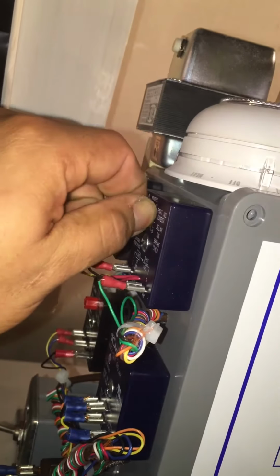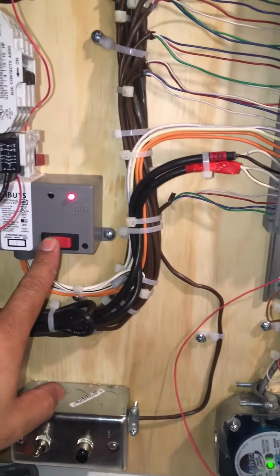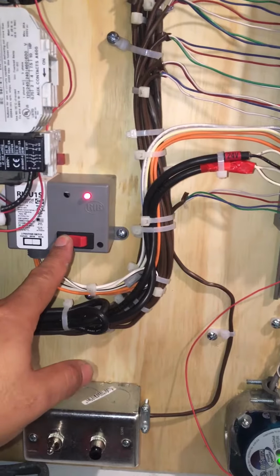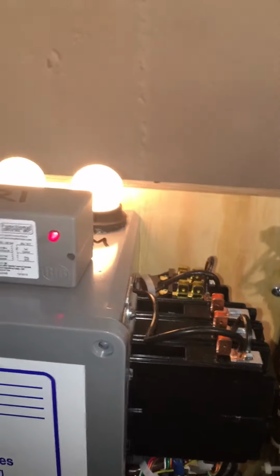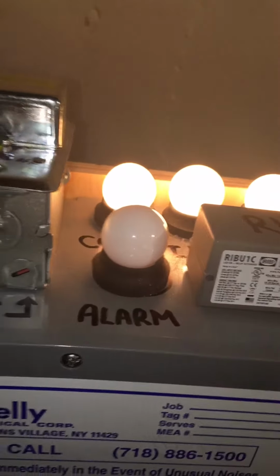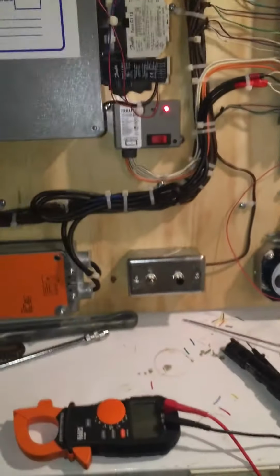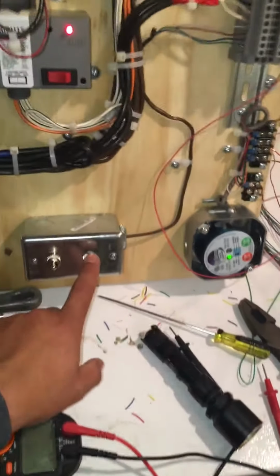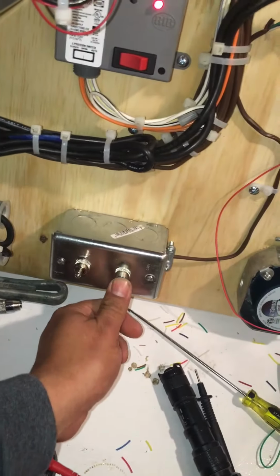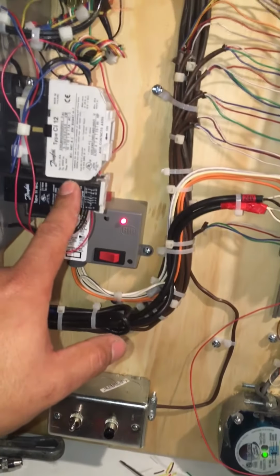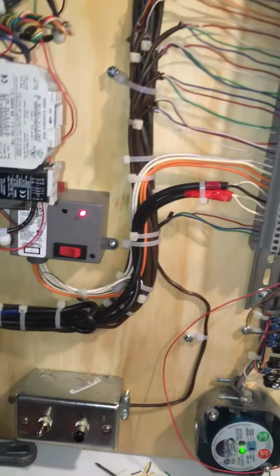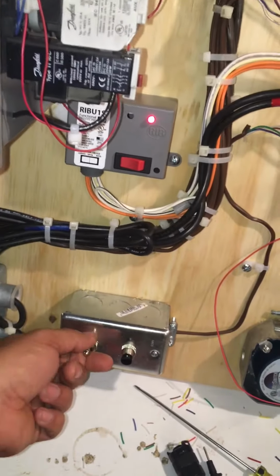I bring back down the delay on break timer. The delay on break timer is completely down. I'll flip this into the hand just to show that it works on hand. There that goes. There goes the compressor. So basically the only features here I haven't showed is that I got this momentary start switch to engage the condenser fan, the condenser pump if I wanted to, with a stop switch over here.